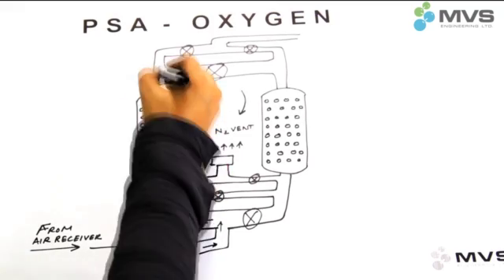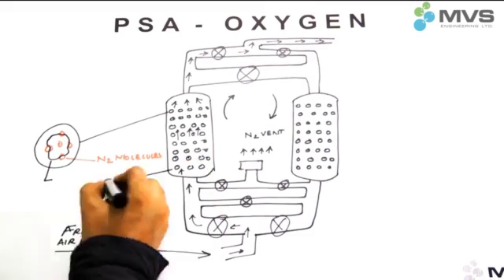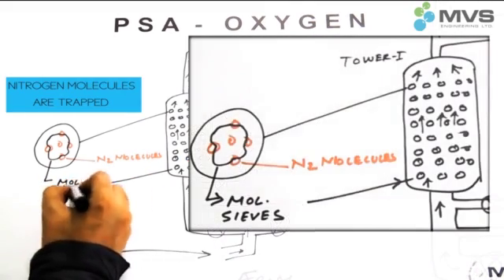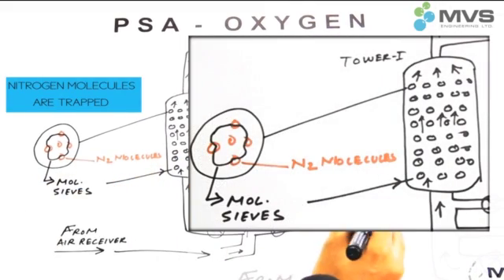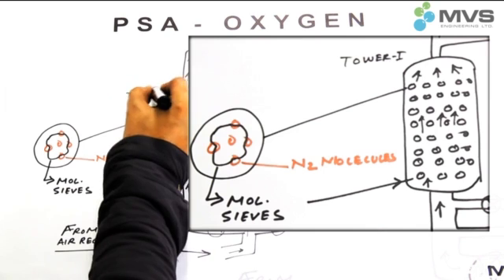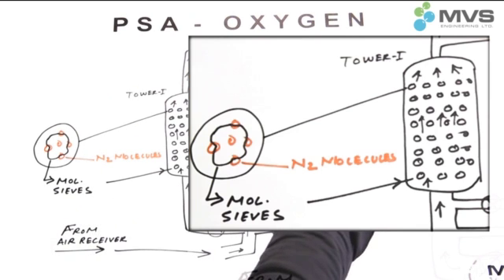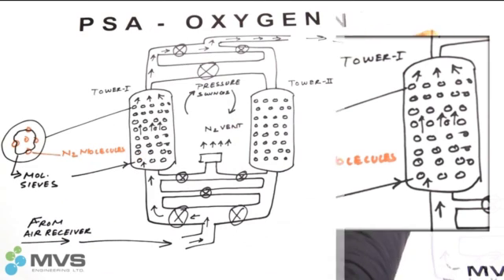Compressed air is passed through tower one. This compressed air pressurizes the tower. The nitrogen gets absorbed by the molecular sieves, while the oxygen gas is delivered as a product gas. Oxygen production continues until tower one gets saturated with nitrogen molecules.